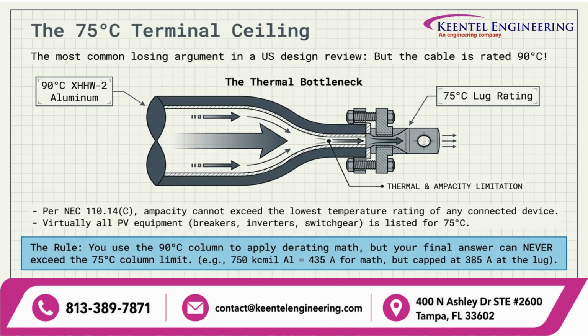For example, a 750 kcmil aluminum conductor starts at 435 amps for math, but is hard-capped at 385 amps at the termination.